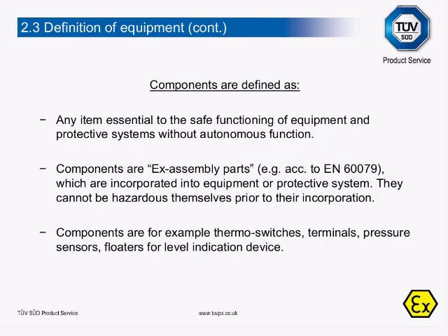Components are defined as any item essential to the safe function of equipment and protective systems without autonomous function. Components are EX assembly parts which are incorporated into equipment or a protective system. They cannot be hazardous themselves prior to their incorporation. Examples of components include thermal switches, terminals, pressure sensors, and floaters for level indication service devices.